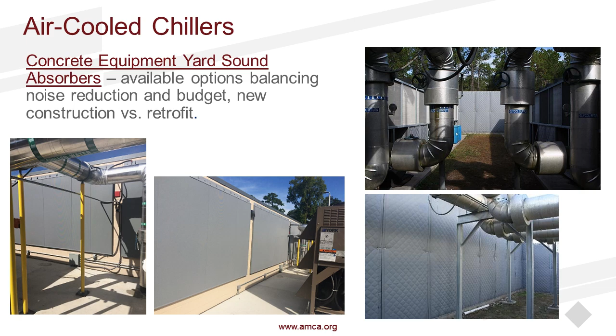Another option to stay within budget, or where there's no budget at all, are outdoor quilts, 4-inch thick quilts that are factory quilted and can be mounted on furring strips behind with fender washers and lag screws, softening the inside of that equipment yard. Once again, taking down those reverberations, usually obtaining about an 8 to 10 dBA reduction. It's a cost-effective way of softening those.